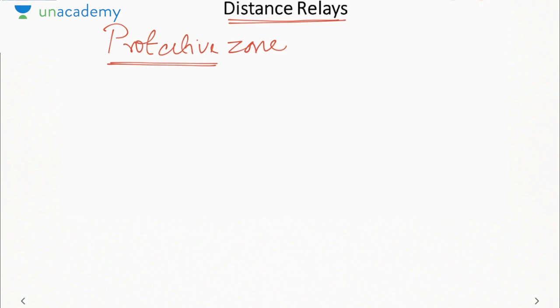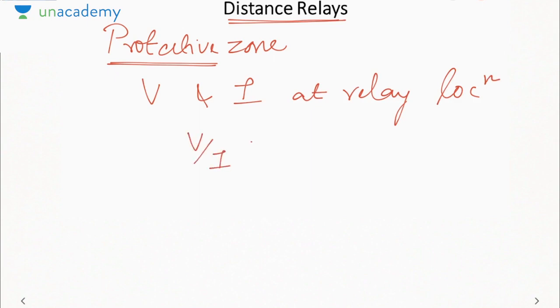These operate based on the distances, but how can a relay or a switch measure distance? So actually, the relay does not measure the distance. Rather, it measures voltage and current at relay location. Now, V by I will give me a measure of impedance, which is directly proportional to length or distance. And hence, these relays can indirectly operate on the basis of distance. Is it fine? So that is how a distance relay operates. It operates on the ratio of V and I. Remember, the distance relay can never measure the distance or the impedance. Rather, it measures the ratio of voltage and current at the relay location.